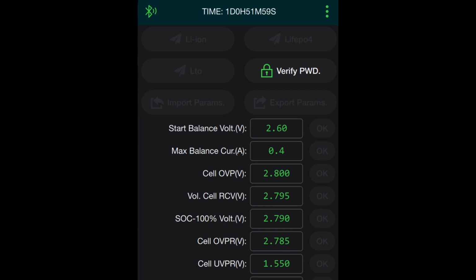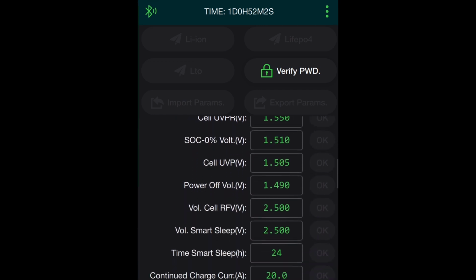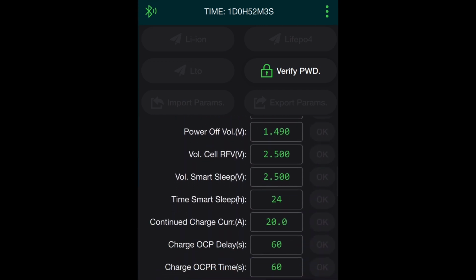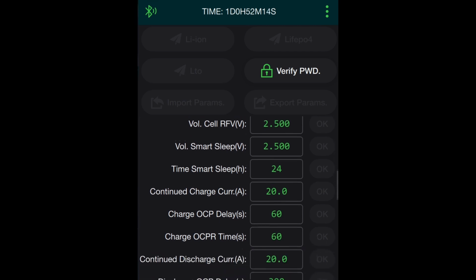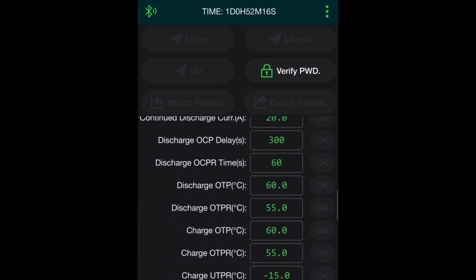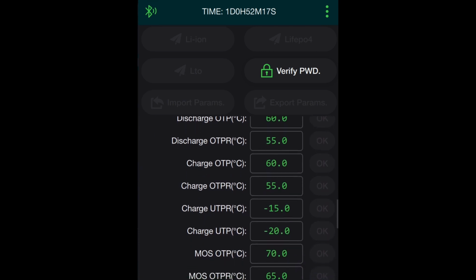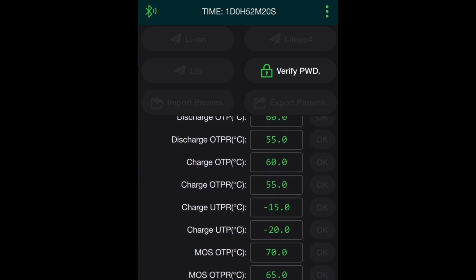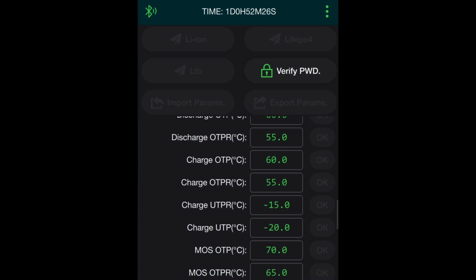The cell undervoltage protection reset is at 1.55 volts. A 0% charge is at 1.51 volts per cell. The cell undervoltage protection is set to 1.505 volts. The battery shuts down at 1.49 volts per cell. The continuous charge current is set to 20 amperes. We can see that the charge under temperature protection is set to minus 20 degrees Celsius. This is an advantage of this type of battery.